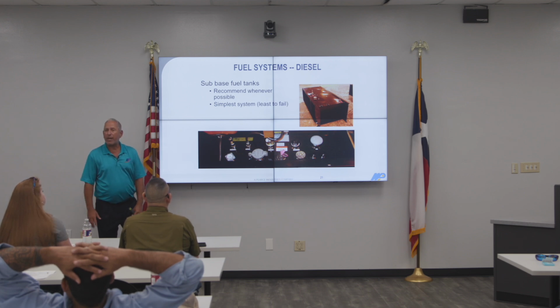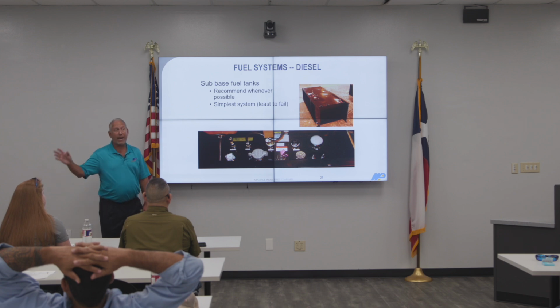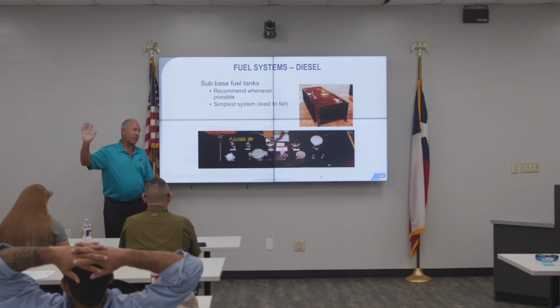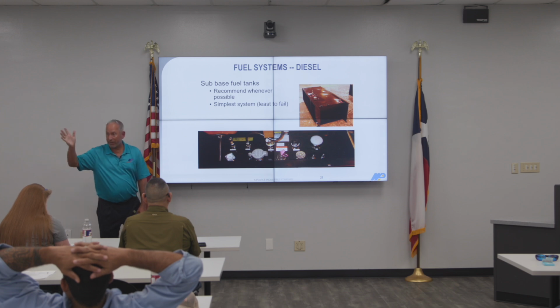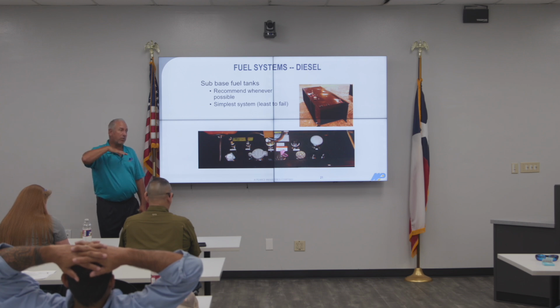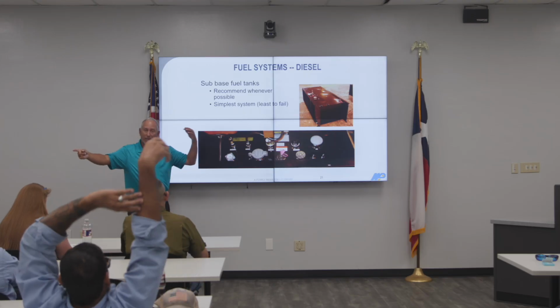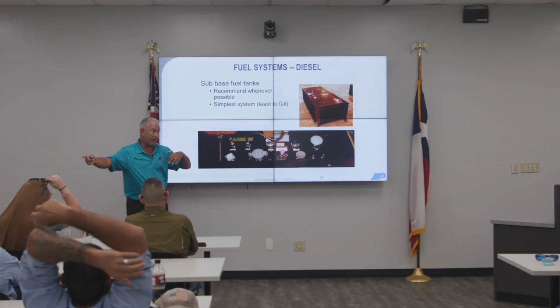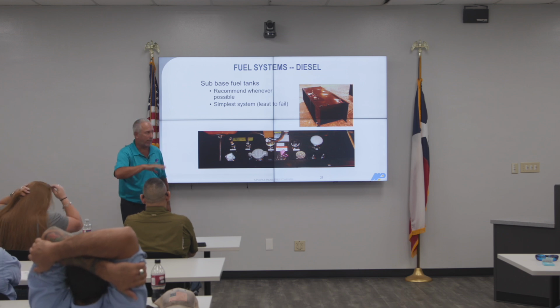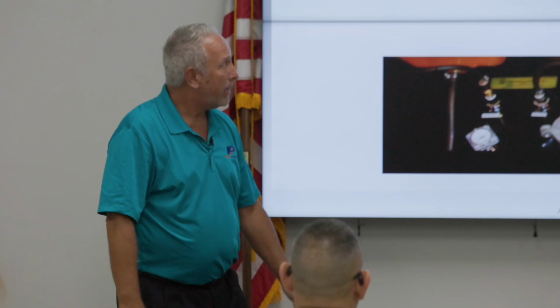Every now and then you'll see a bigger system where they may have a large diesel tank on site, running boilers and whatever, so they may opt to use that main tank to run the emergency generator. Generally what they'll do is put what we refer to as a day tank near the gen, maybe 100, 200 gallons. That tank will call for diesel fuel from the main tank, and then the generator will pull from that day tank. Tends to be a little bit more complicated, but this is typically what you see.